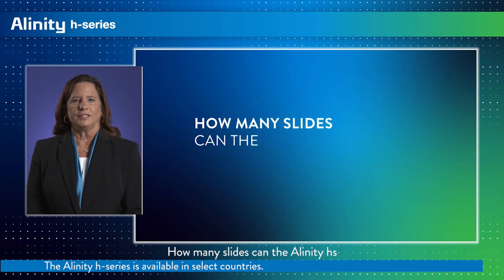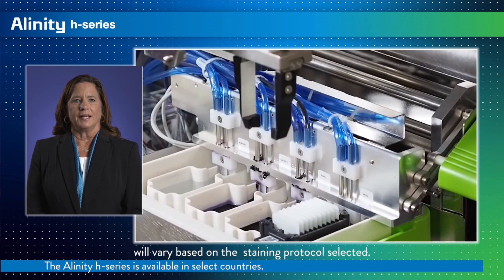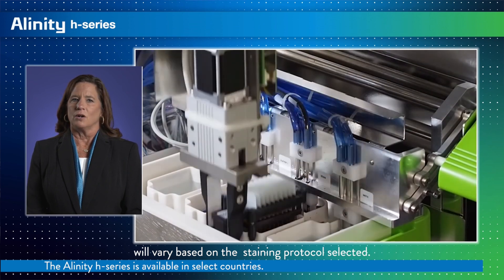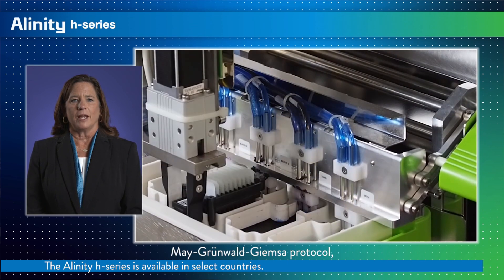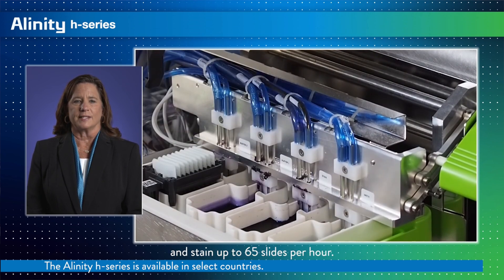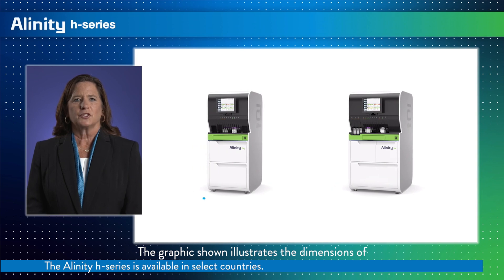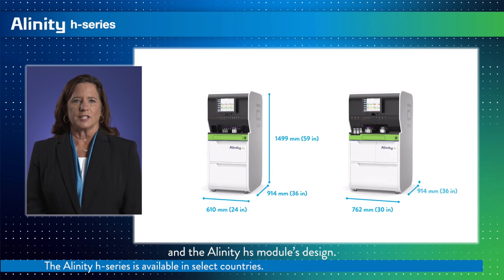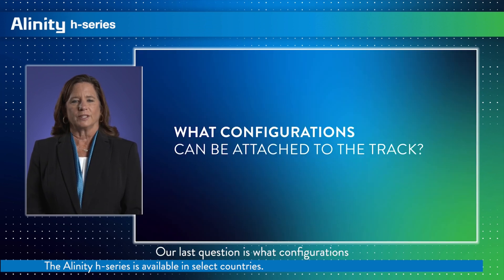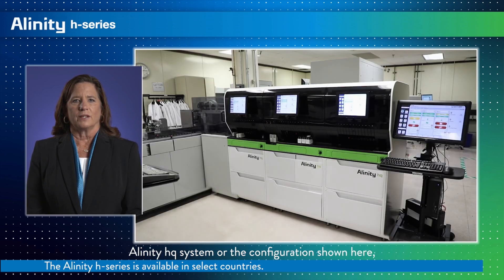How many slides can the Alinity HS, the Slide Maker Stainer module, make in an hour? The designed throughput of the Alinity HS will vary based on the staining protocol selected. For example, if using the default May-Grünwald-Giemsa protocol, the Alinity HS is designed to smear and stain up to 65 slides per hour. What are the dimensions of the modules? A graphic illustrates the dimensions of both the Alinity HQ and the Alinity HS module's design. Our last question: what configurations can be attached to the track? Currently, the two configurations designed to be available are the standalone Alinity HQ system, or the configuration shown here, which has two Alinity HQ modules with one Alinity HS module.